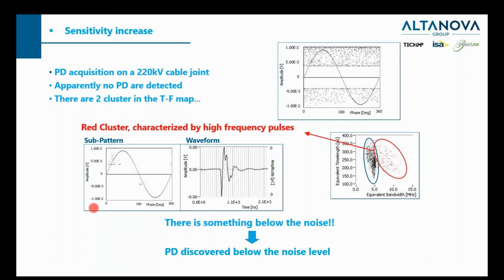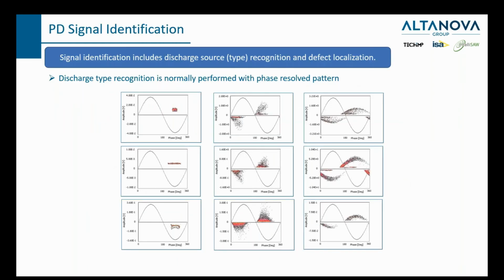Here's a little summary about the PD signal separation, especially the technology advantage that we use the TF map to separate the signals from different sources and to recognize signals from different sources. And PD source identification, I think that's another big advantage. Signal identification includes two parts. The first part is to recognize the type of discharge. This part is performed with the phase resolved pattern.